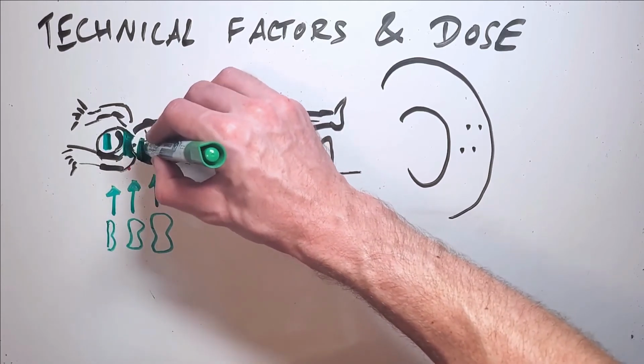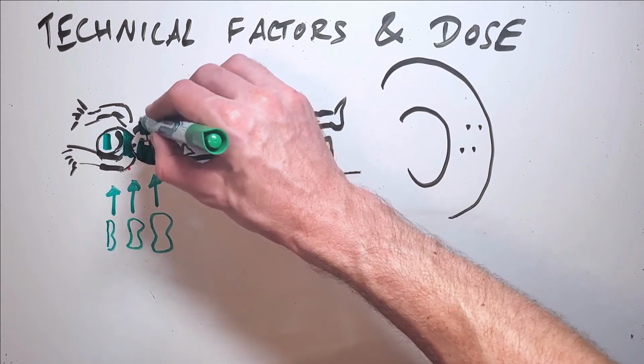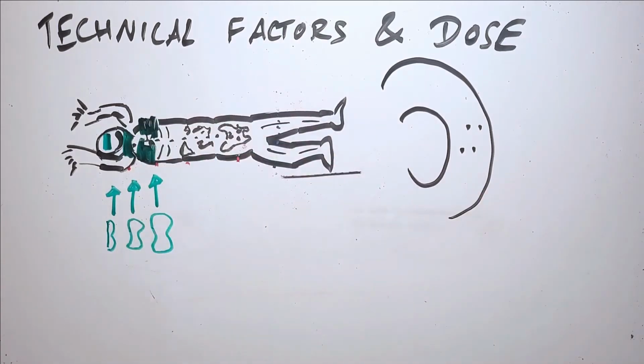Modern scanners are integrating different ways to achieve the same thing without the bismuth shielding by simply reducing the MA when the tube is in front of the patient, so a smaller proportion of the overall dose to the patient will enter from the anterior surface. This is coupled with regular modulation of MA that decreases in the anterior-posterior direction and increases in the lateral direction.